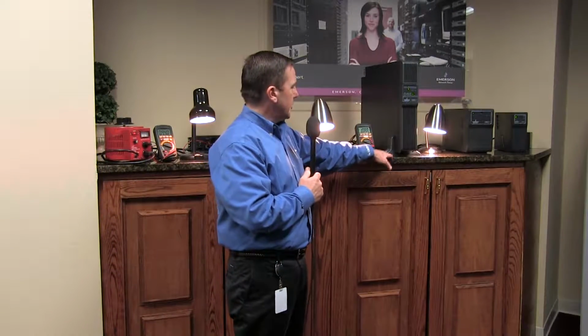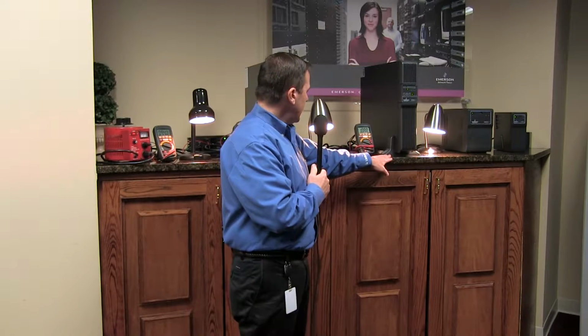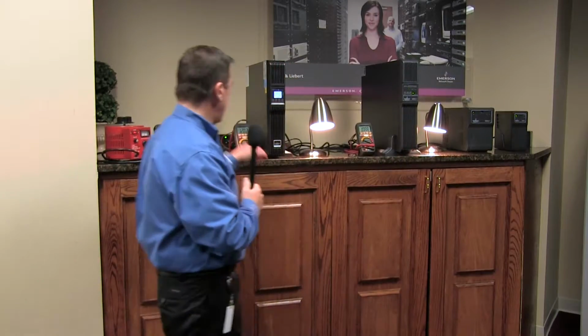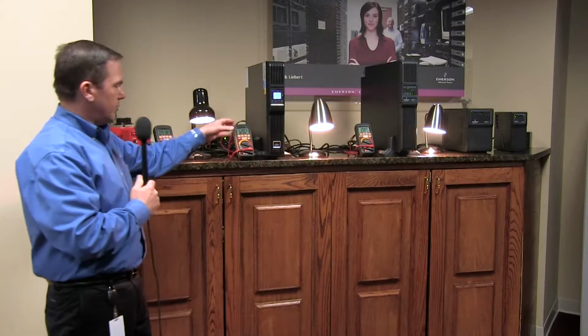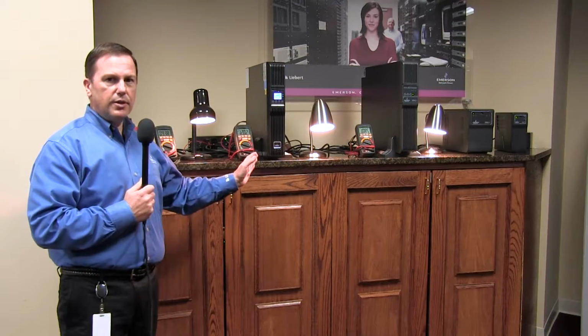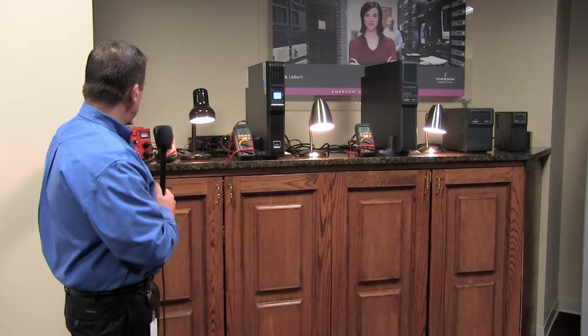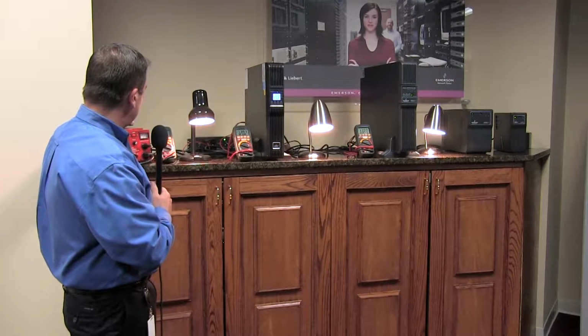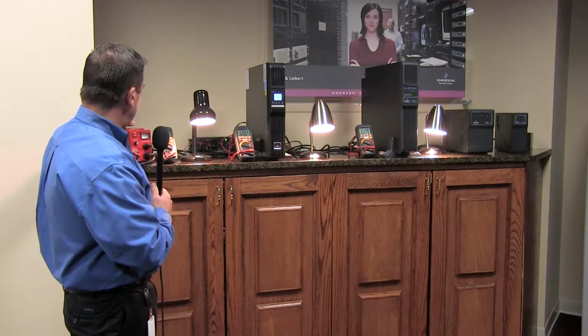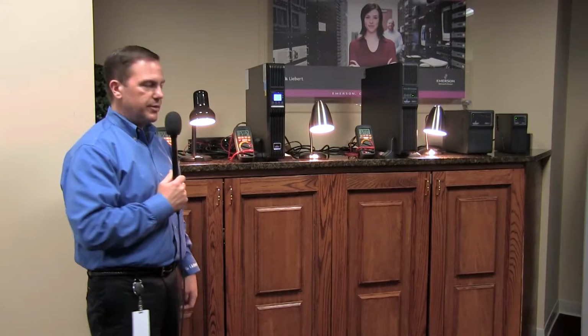You may have heard some clicking, seen some flickering in the light bulb here. We're now down to 108 volts on the output, so our light bulb here is actually dimmer than the bulb plugged into the double conversion UPS. What this means is that your servers and network equipment are not getting the optimum operating voltage. If we take our voltage back up to 120 volts, which is normal, you will notice that all three of the light bulbs are now shining at the same relative intensity.